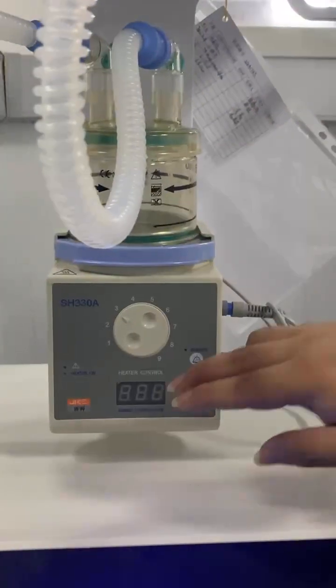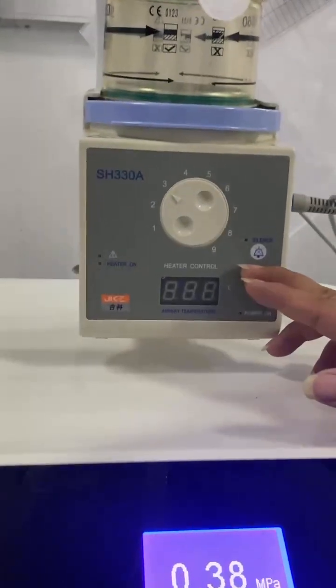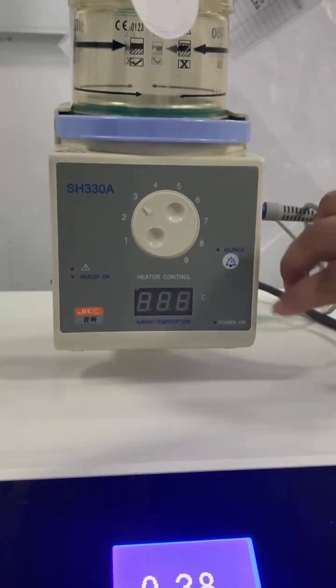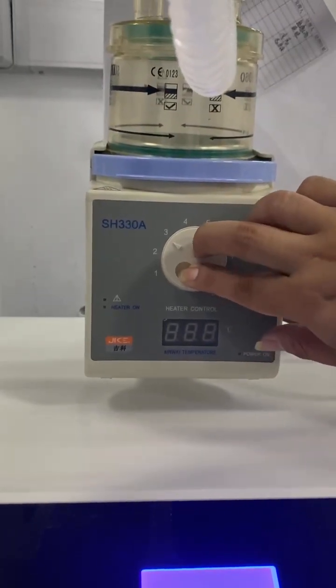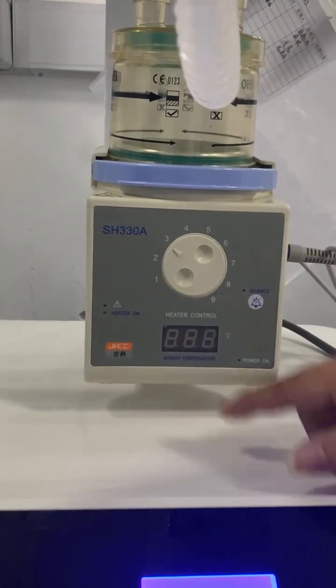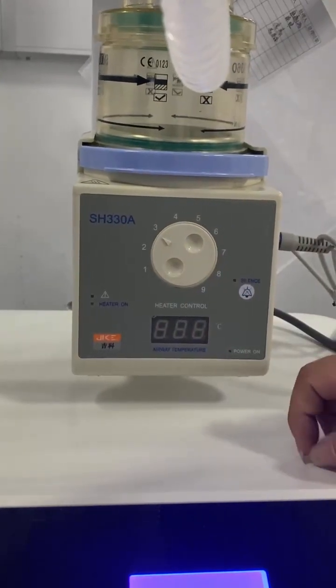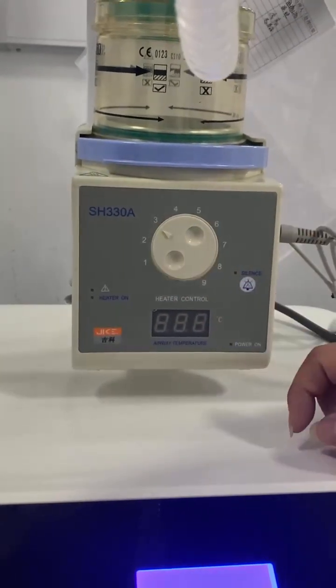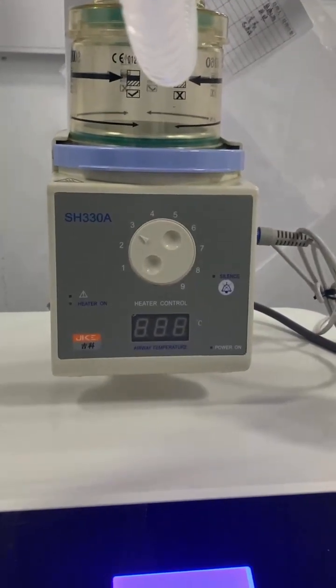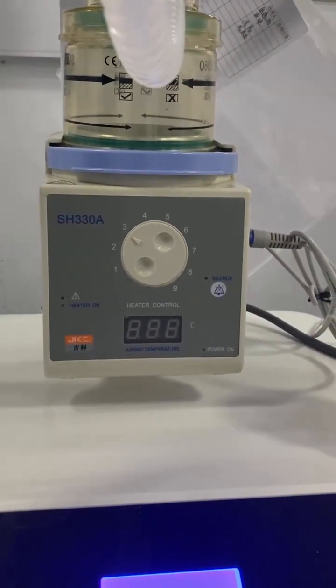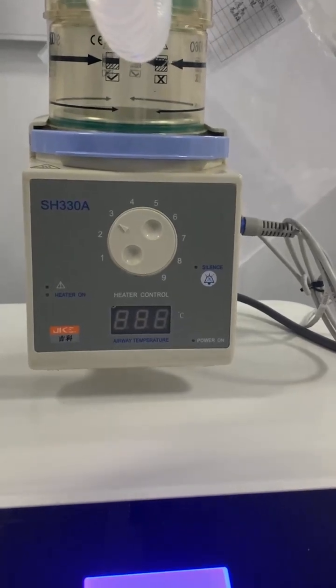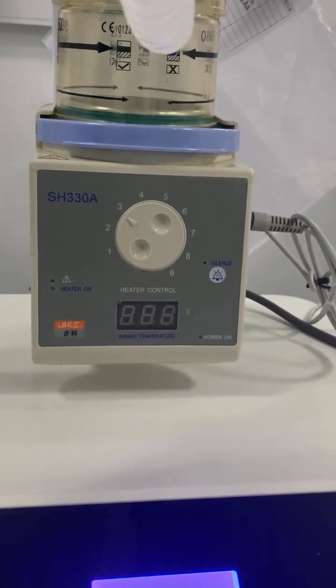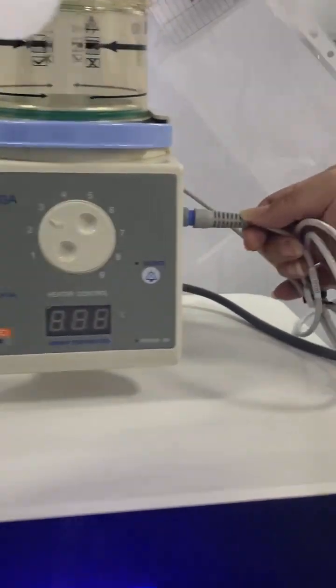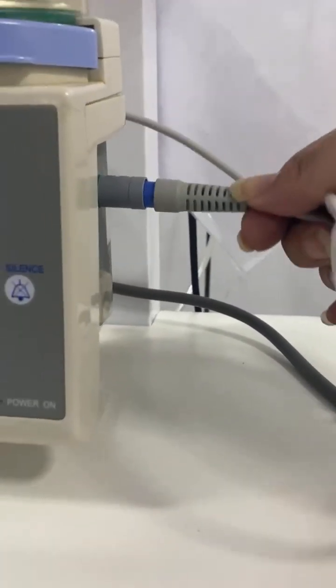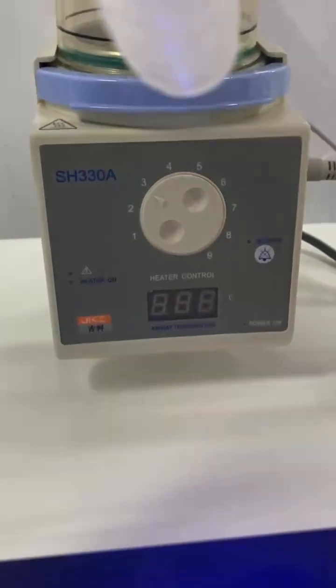After you put in the water, then we will connect with the base and we just do the adjusting here. And usually we use our 2 fingers to adjust very easily, and we always choose between 2 to 3, because usually if the setting parameter is from 2 to 3, it means the temperature from the pipeline will be around 37 degrees. It's around the body temperature, so the patient will be safest and most comfortable. So it is very easy to use the machine. And here is connecting the temperature probe sensor, and the temperature will be shown by the digital meter very clearly here.